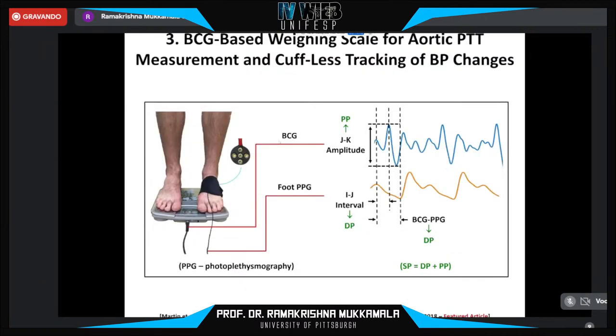So in parallel with the modeling, we developed a BCG-based weighing scale for cuffless tracking of blood pressure changes. The system includes an adjustable strap integrated on the scale to measure a photoplethysmography, or PPG, waveform from the foot in addition to the BCG waveform. So two waveforms via a single recording device.